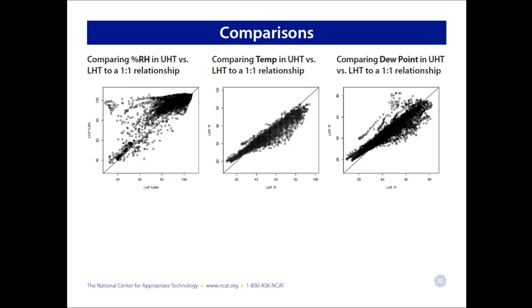So dew point, in the last graph here on the far right, followed a similar trend to the temperature because it's tied in with the temperatures. It's figured on the temperature. And the upper high tunnel had a higher dew point at lower temperatures, and it had a slightly lower dew point at higher temperatures. So this is just another way to look at the data and make a few interpretations of it.